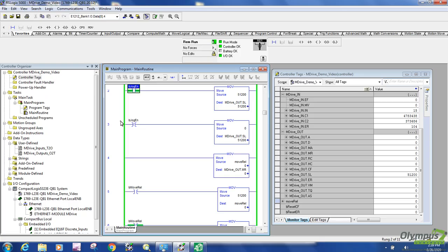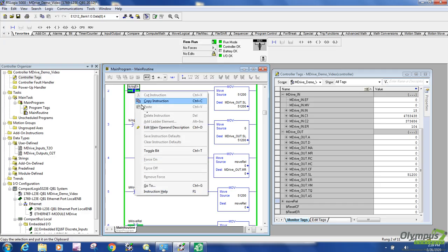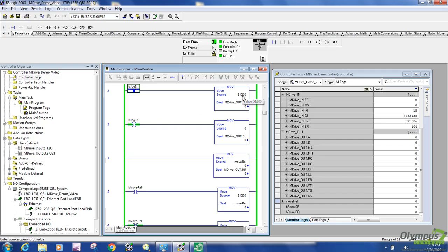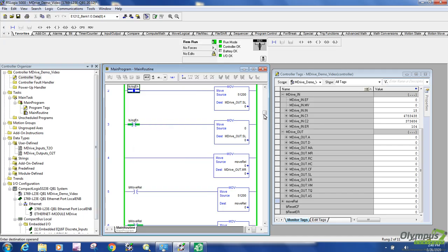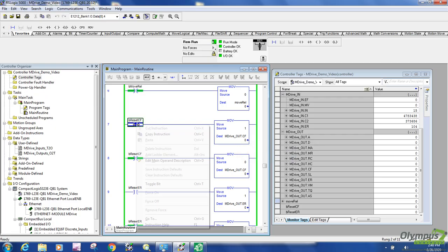There are dozens. To recover from this state, you'll notice that if we toggle off the slew command and then toggle it back on, the motor's not actually going to move. That's because our locked rotor flag is set and we need to reset that error. So in order to do that, we can first turn off our jog command and use our function blocks to clear the locked rotor with the clear locked rotor flag.